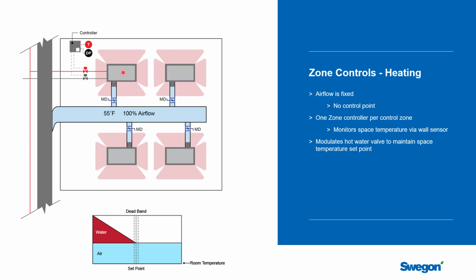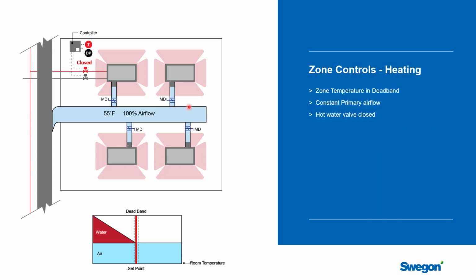Typically, a chilled beam is closer to somewhere between 0.5 and 1 GPM of hot water. So this is going to be somewhere between 2 and 4 GPM for the zone that you see here with 4 beams in it. So now let's talk about what happens during the controls. So you can see down here, we are inside the dead band, so this space is satisfied. It's not hot, it's not cold. The temperature that's being read is basically matching the set point, so the hot water valve would be closed.